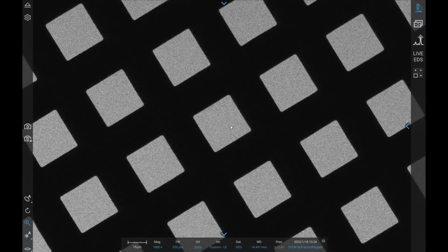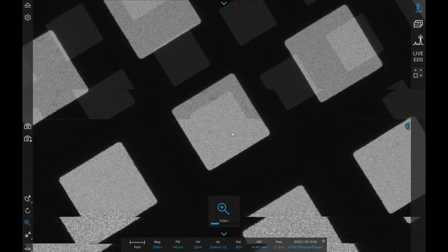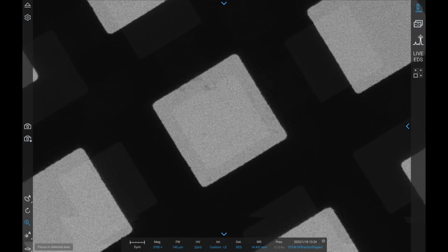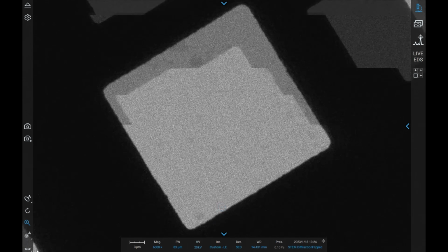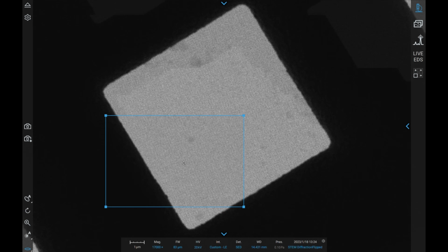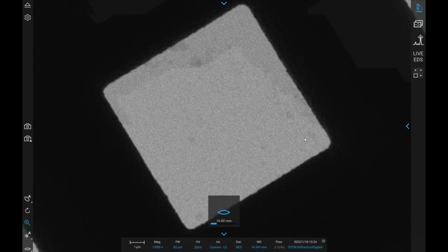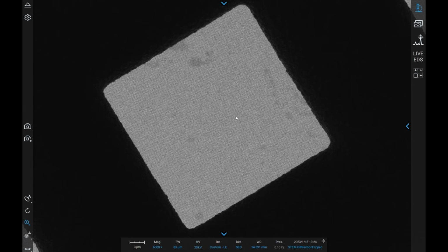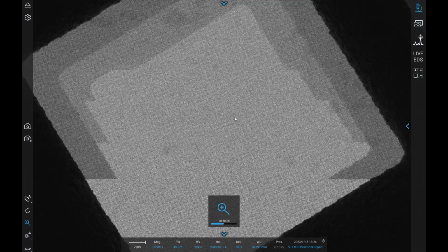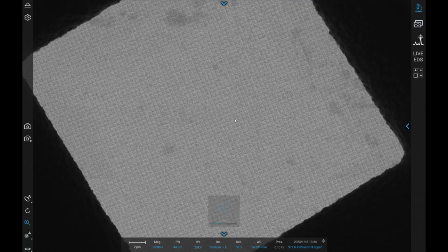If we turn on the secondary electron detector, kind of the opposite happens. The grid goes dark, which is, again, good, because that means we're not seeing any secondary electrons bouncing off the grid itself and making it to the detector. But the space in between the grid lights up, because these are all the electrons that are passing through, hitting that conversion plate at the bottom, and then being picked up by the sensor.